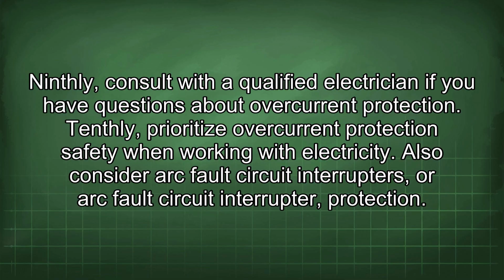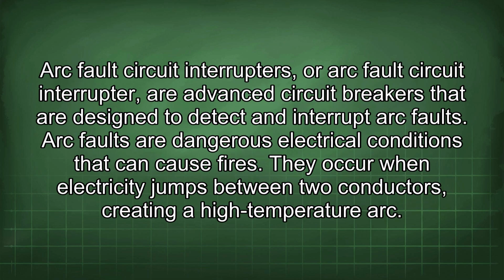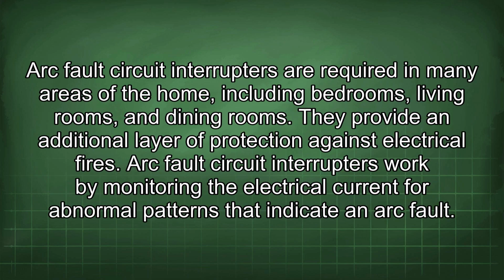Also consider arc fault circuit interrupter, or AFCI, protection. Arc fault circuit interrupters are advanced circuit breakers that are designed to detect and interrupt arc faults. Arc faults are dangerous electrical conditions that can cause fires. They occur when electricity jumps between two conductors, creating a high temperature arc. Arc fault circuit interrupters are required in many areas of the home, including bedrooms, living rooms, and dining rooms. They provide an additional layer of protection against electrical fires.